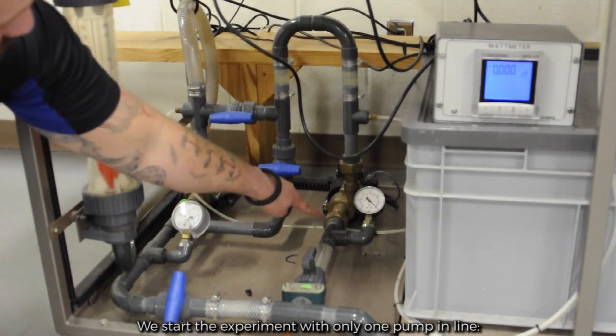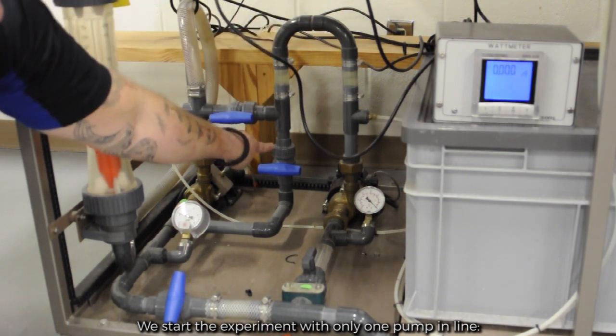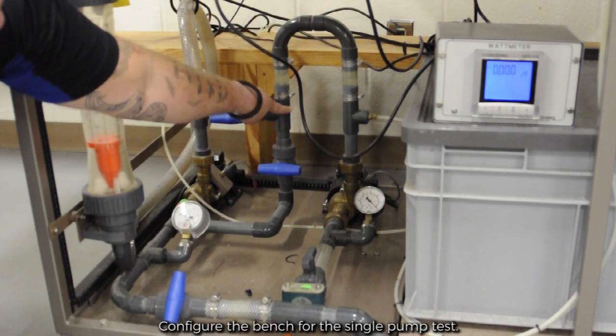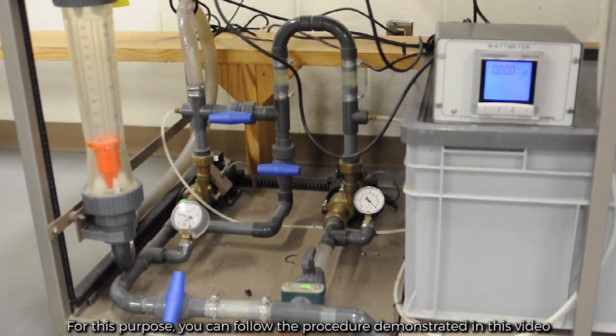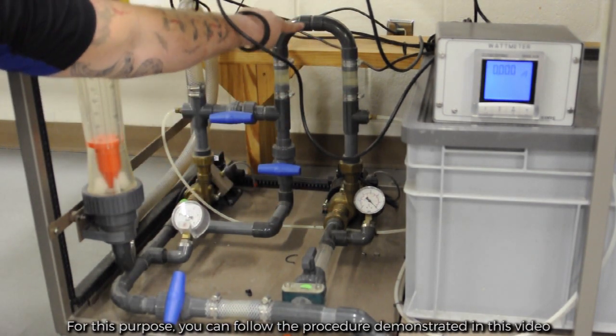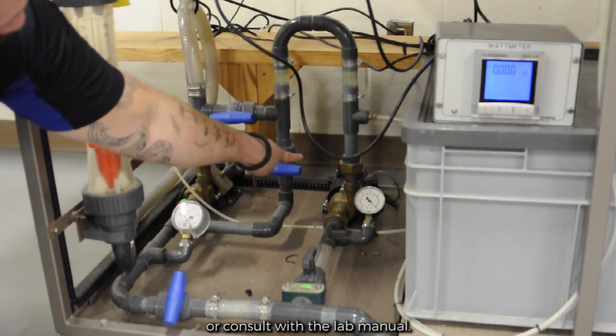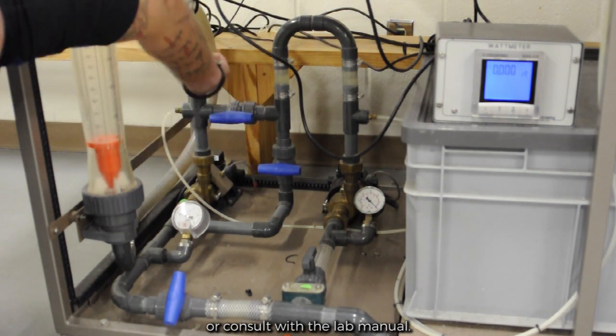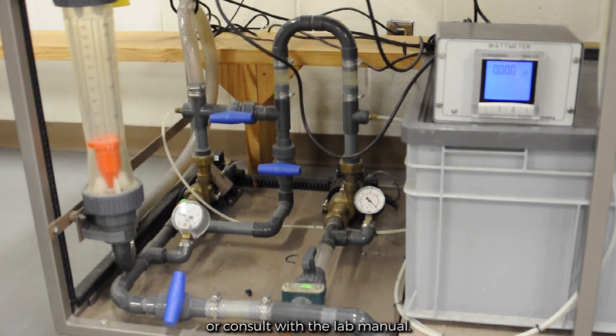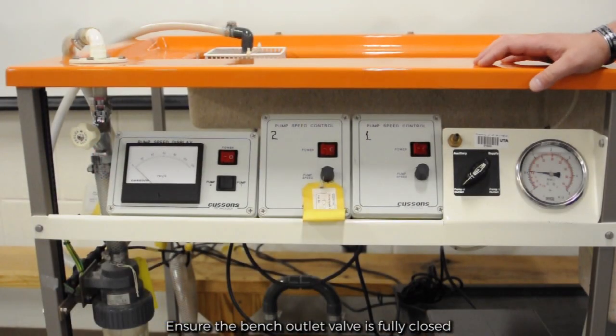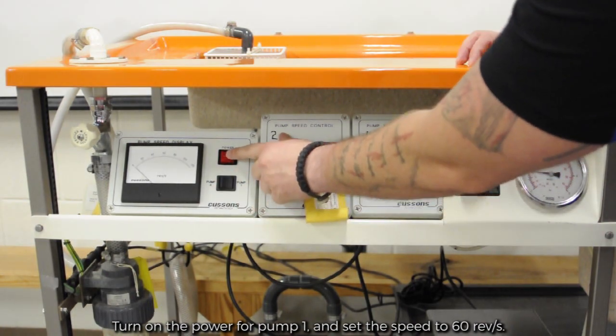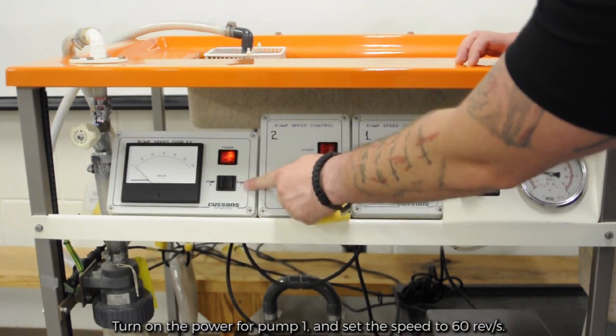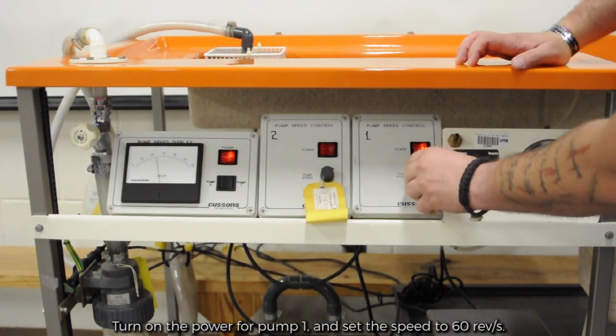We start the experiment with only one pump in line. Configure the bench for the single pump test. For this purpose, you can follow the procedure demonstrated in this video or consult with the lab manual. Ensure the bench outlet valve is fully closed. Turn on the power for pump one and set the speed to 60 revolutions per second.